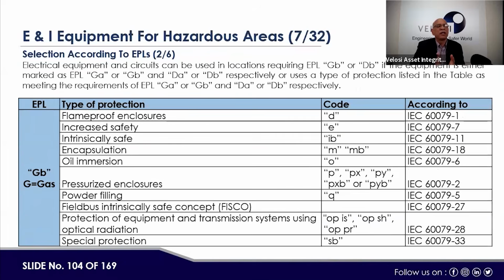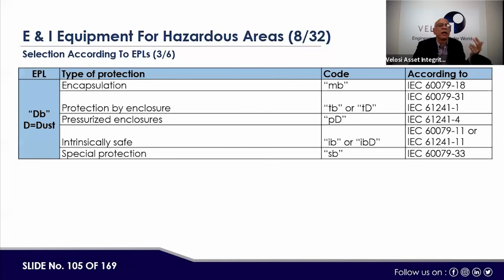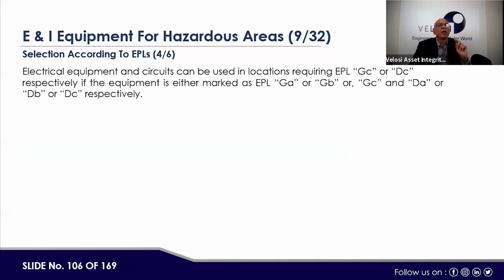Now, if there is a GB class, accordingly there is a type of protection code and an applicable standard. Similarly, for the type DB, the same continues. And then accordingly, we go for EPLs. The message is: the higher class can be used in the lower class, but the lower class cannot be used in the higher class. The EPL class is important in the system.